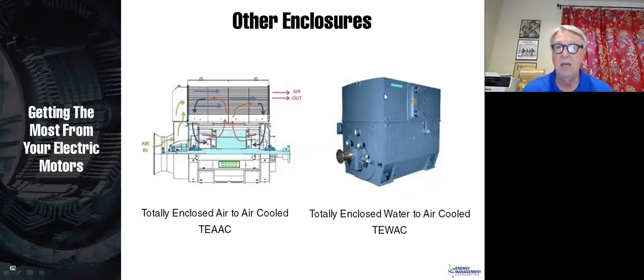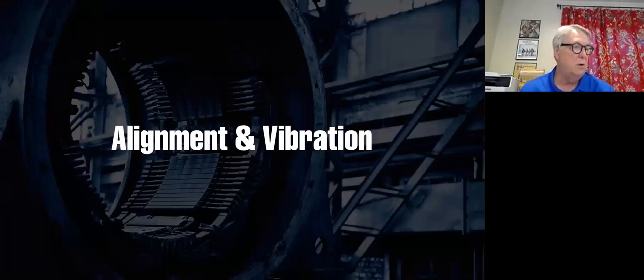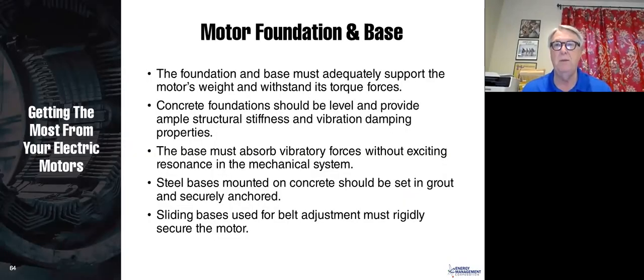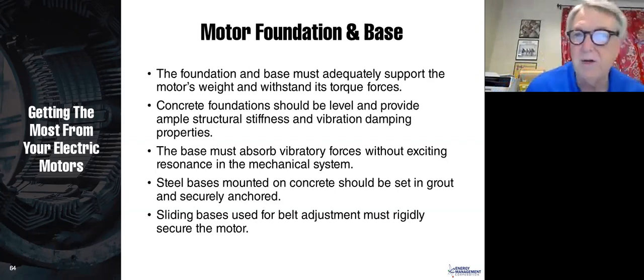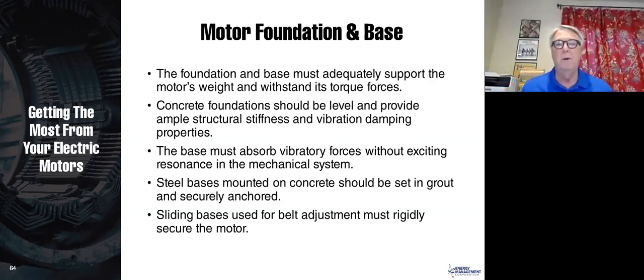But you have to have a heat exchanger in one case cooled by air, in the other case cooled by plant water. Now let's get into alignment and vibration. We've got about 15 minutes, so we'll do the alignment pretty quickly, because alignment is very specialized.